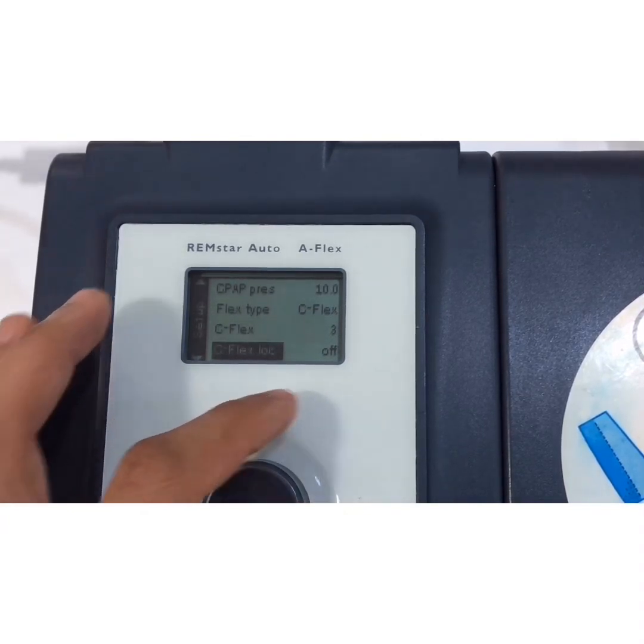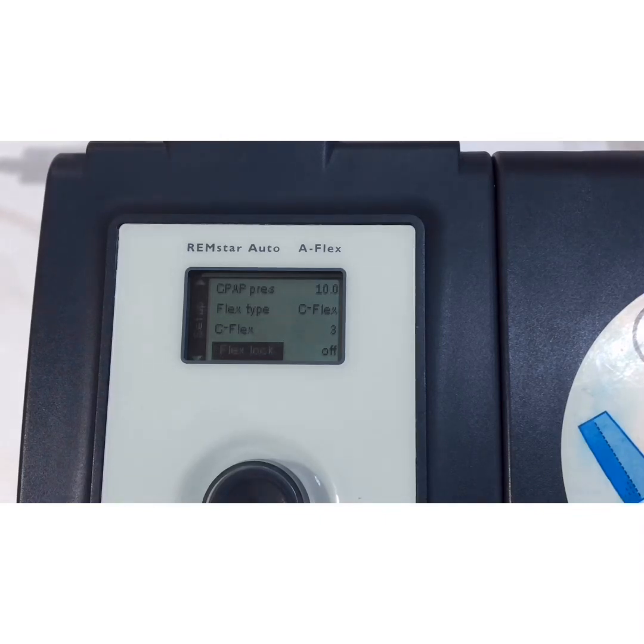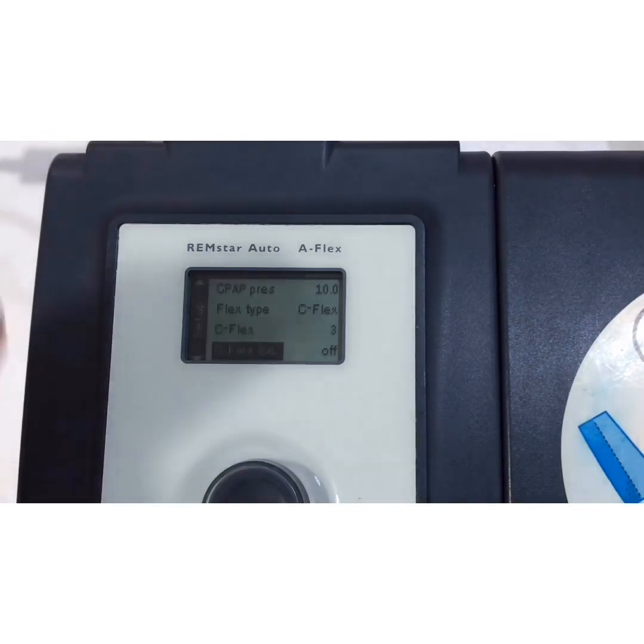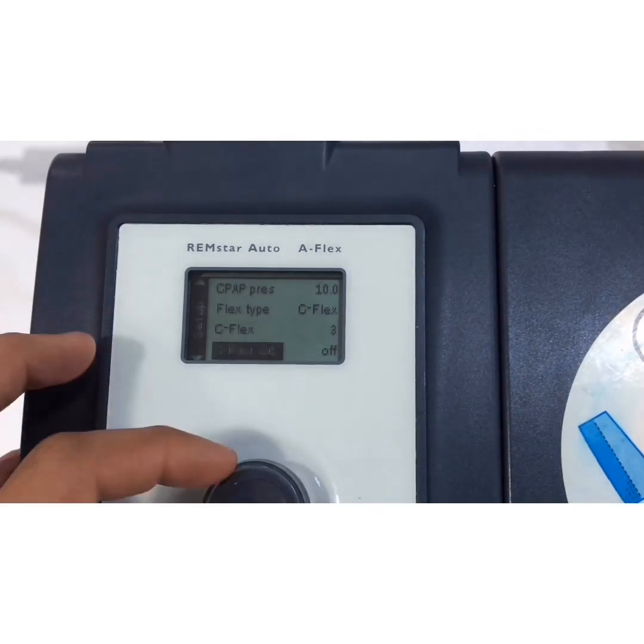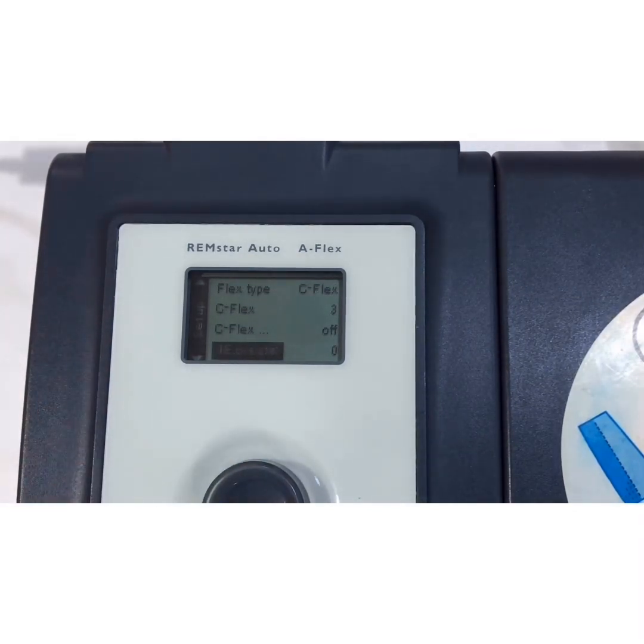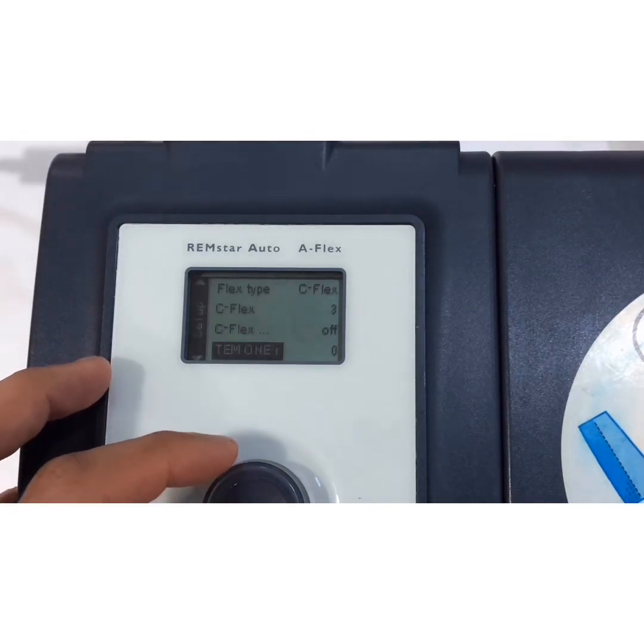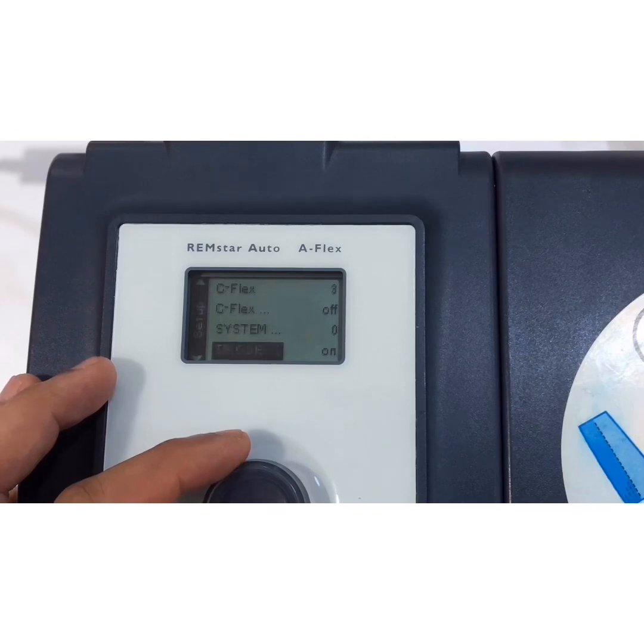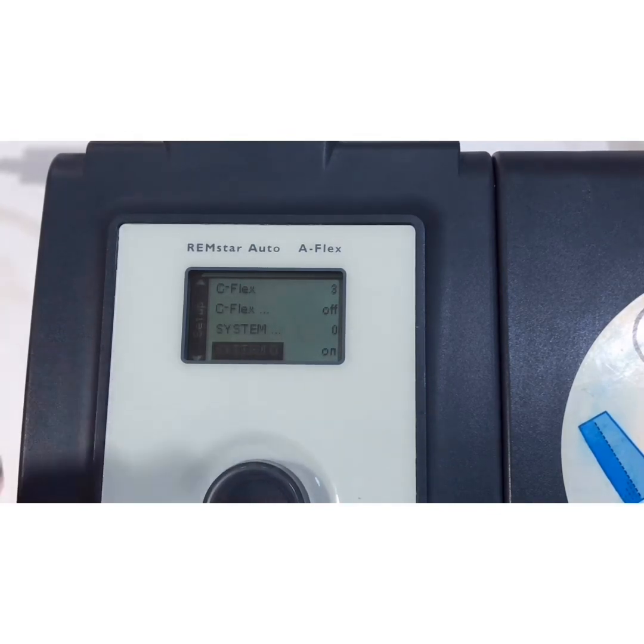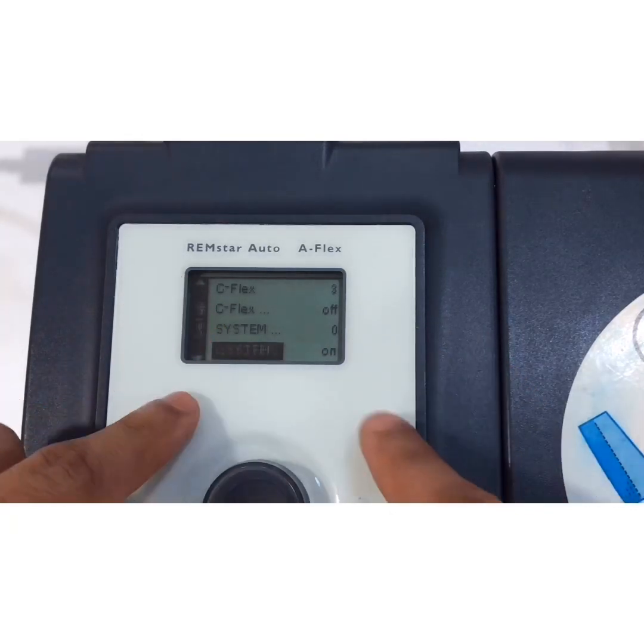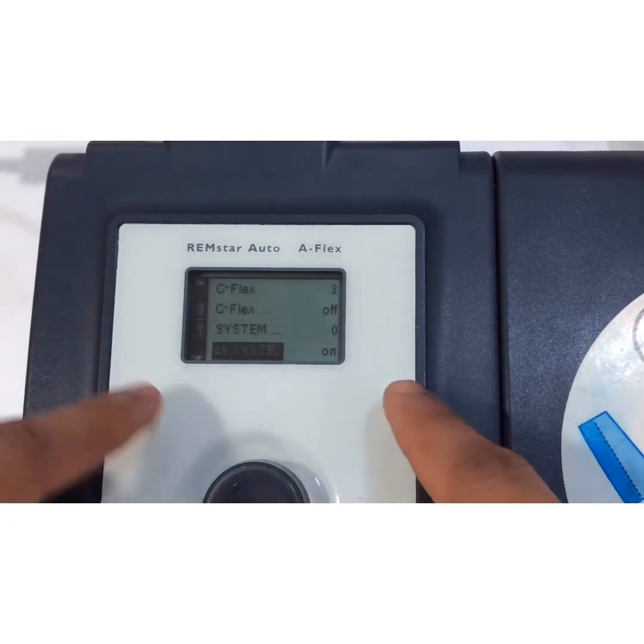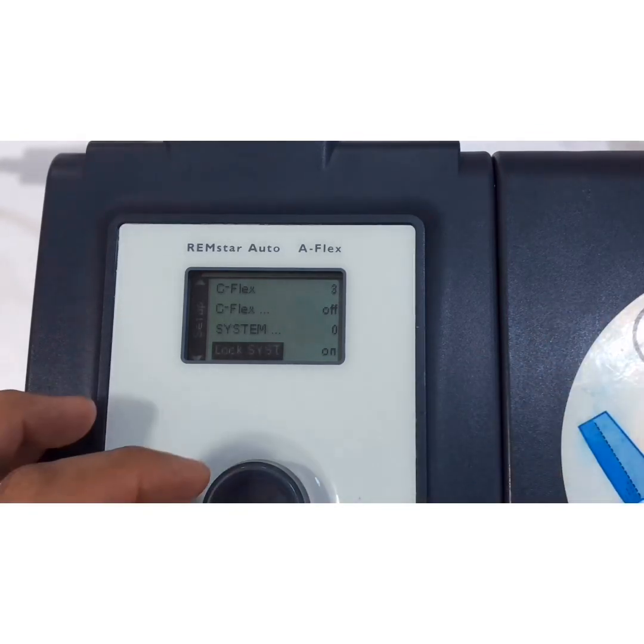C-flex lock, it's off. That means everyone is able to change the flex, the type and the level. System one resistance: do I want the patient to feel some resistance during his exhalation? I would say no, so that's why I will make it 0. Here what we have, can I say one more time? I cannot really read. Lock the system, yes, of course I want to lock it. For this reason, I did double pushing of 2 buttons when I want to go just to change my settings.